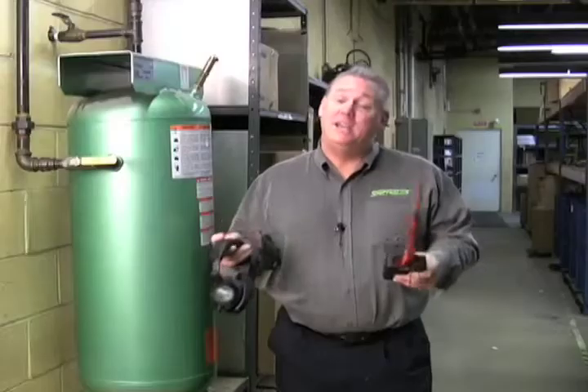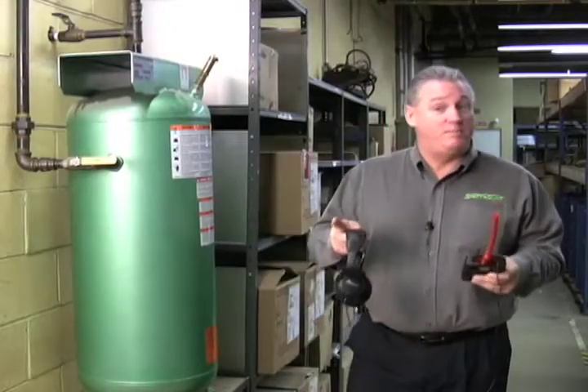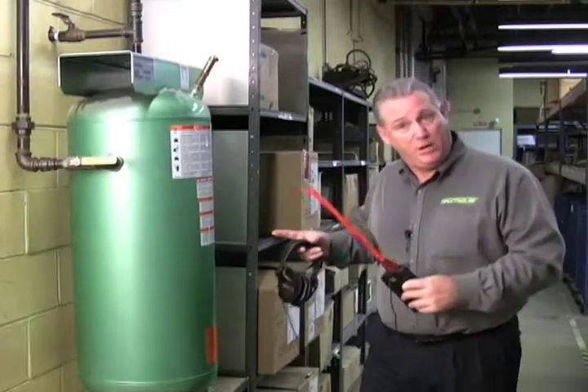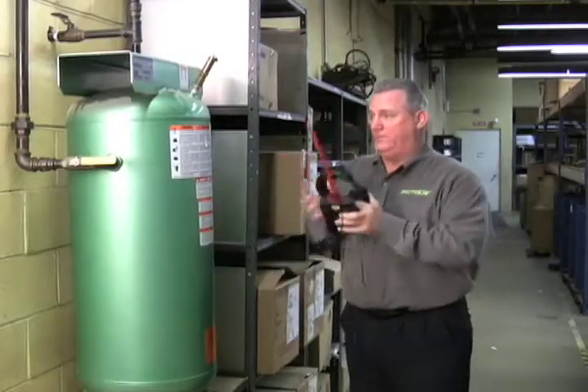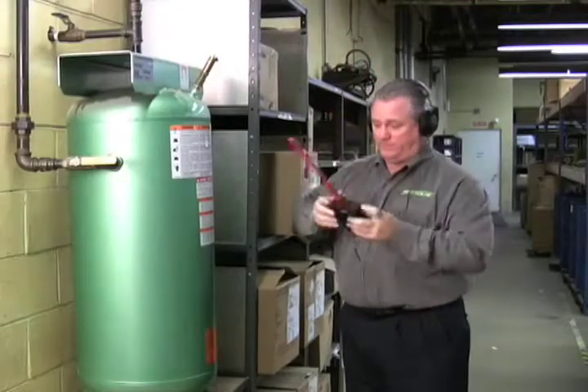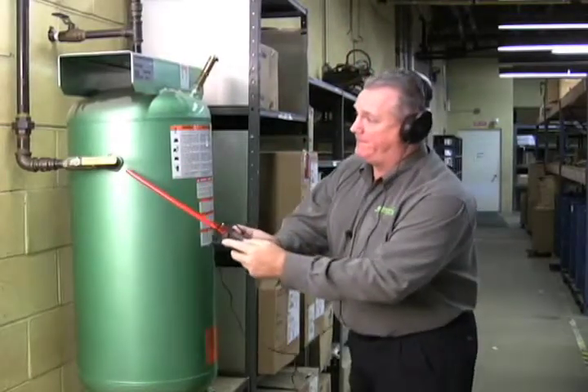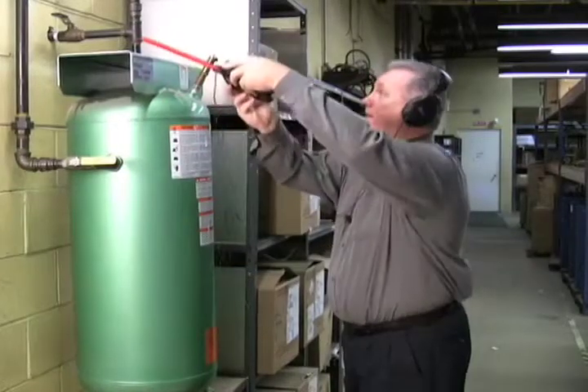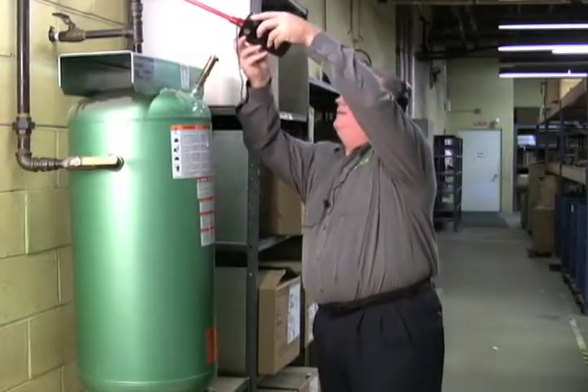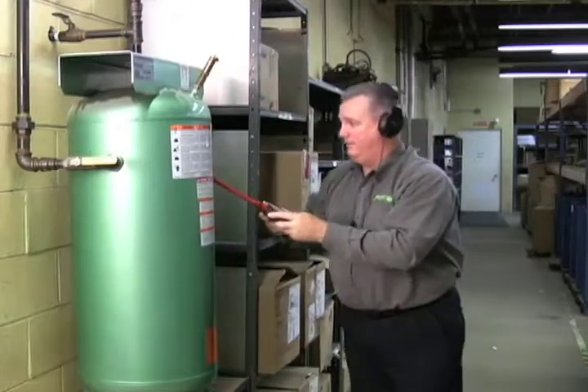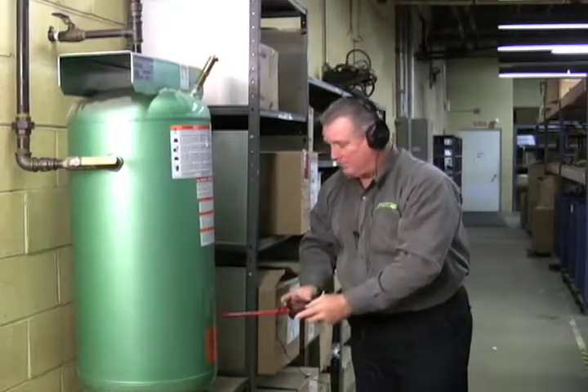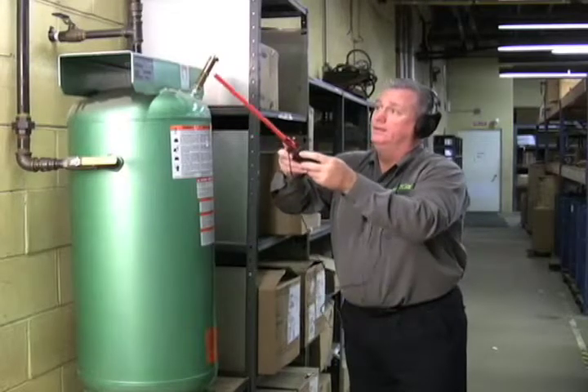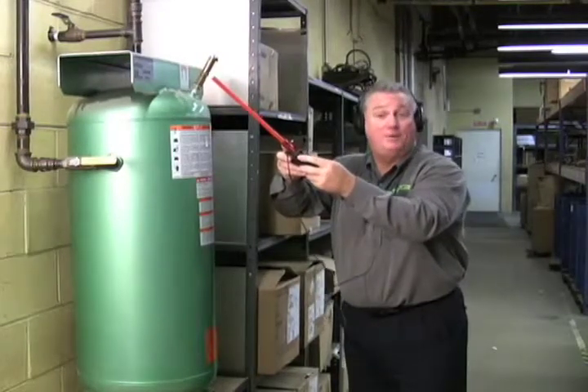Now, let's get to the real fun and put the Marksman through its paces. Well, today nearly every plant utilizes compressed air. And believe it or not, compressed air is the most expensive utility. We're at our holding tank in our plant and we're going to test for air leaks right here. Here we go. We've already found one at our pop-off valve.